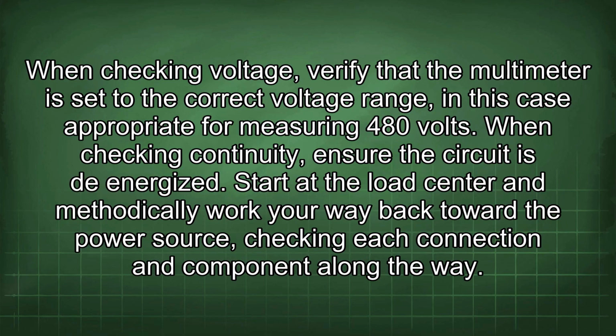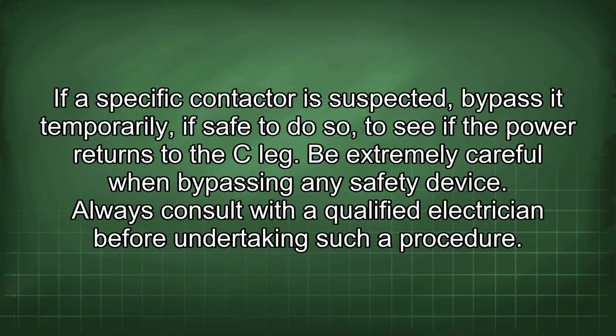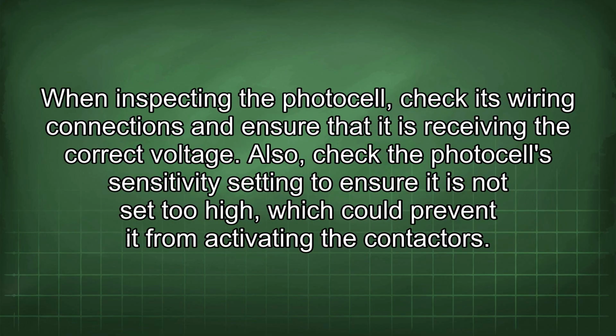If a specific contactor is suspected, bypass it temporarily, if safe to do so, to see if the power returns to the C leg. Be extremely careful when bypassing any safety device. Always consult with a qualified electrician before undertaking such a procedure. When inspecting the photocell, check its wiring connections and ensure that it is receiving the correct voltage. Also, check the photocell sensitivity setting to ensure it is not set too high, which could prevent it from activating the contactors.